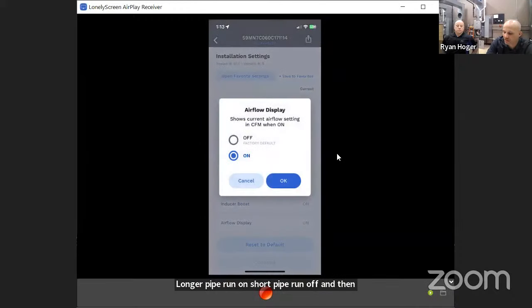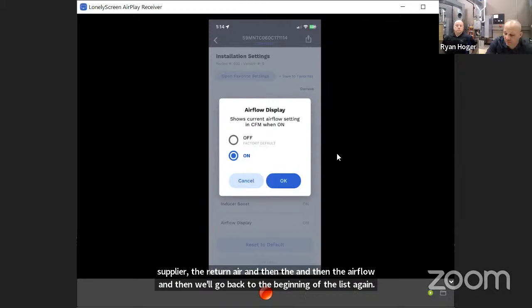The last one is airflow display. That was defaulted off, and I turned it on for this furnace. It shows you the airflow on that little 3-digit screen, rotating between any alarm codes, the mode you're in (heating, cooling, etc.), the supply air, the return air, and the airflow, then back to the beginning of the list. I like to have that on—I don't see any reason to turn it off, but some people are weird and it's off by default. I'd rather have more info than less.